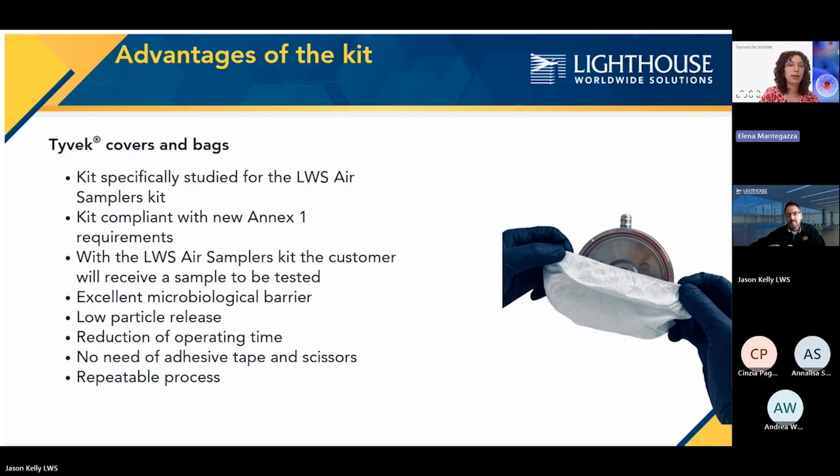Of course, if a customer arrives with a different packaging material, the autoclave cycle has to be revalidated for sure. And we can support them with our documentation from our quality assurance department. Any other type of support that you would offer as subject matter experts, or that would help in a project to offer your consultancy service?